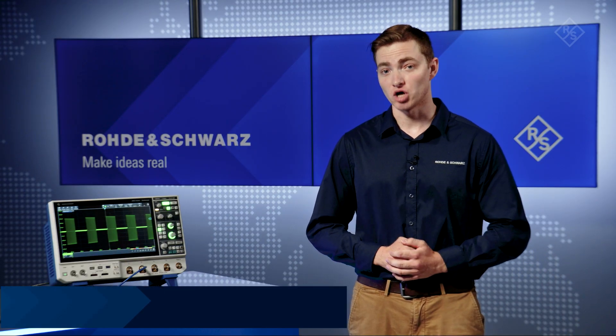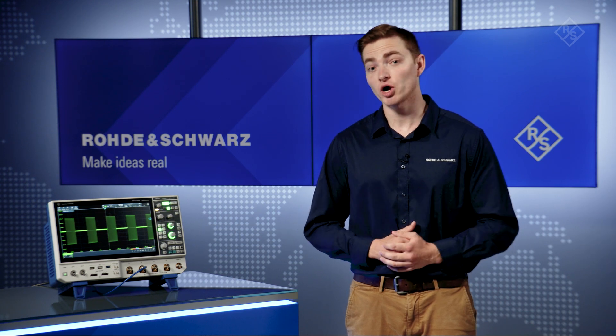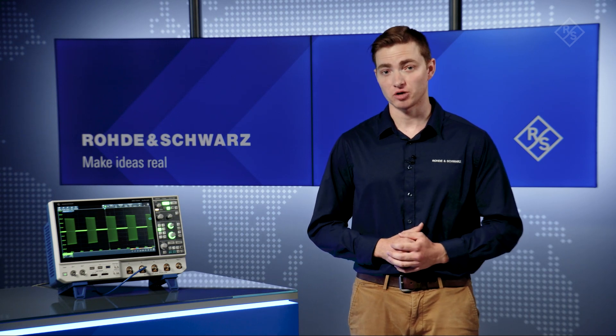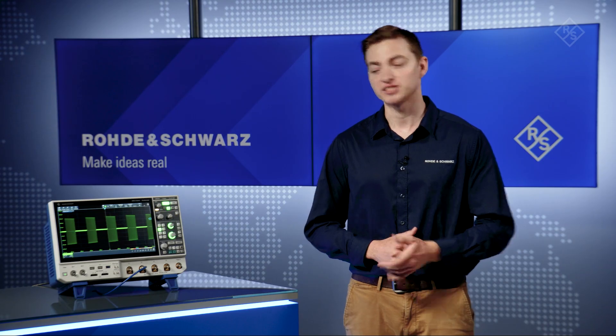Do you wish your oscilloscope could capture longer periods of time accurately? In most oscilloscopes, there's a trade-off between maintaining a high sample rate and capture time. But with the standard 400 million points of memory, or the 800 million points upgrade, the MXO4 series oscilloscopes can capture longer time periods while maintaining a higher sample rate. Let's take a look.